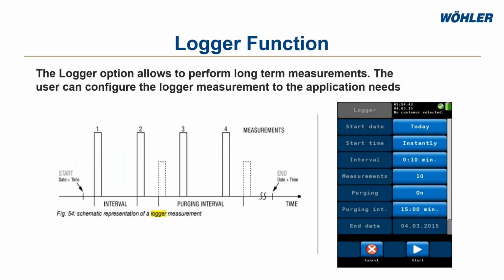Here's the logger function I was talking about earlier. It's used in the A550 if you want to do continuous measurement. Let's say you want to start a test on 11/11 and end it on 11/13 - you can set your analyzer to capture combustion readings every 10 minutes. You can even set it to purge, say every 2 hours, and set that interval. It's a nice feature, especially if you're in a research lab or just want to see what's going on with your boiler over time if it's having issues.